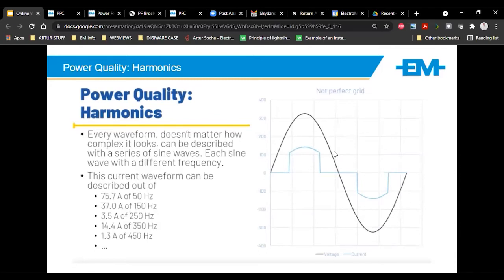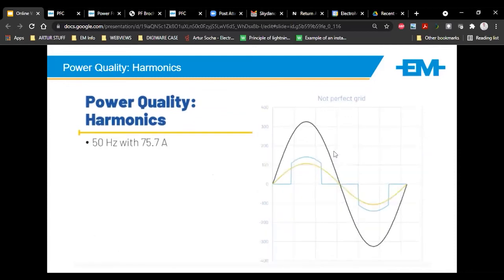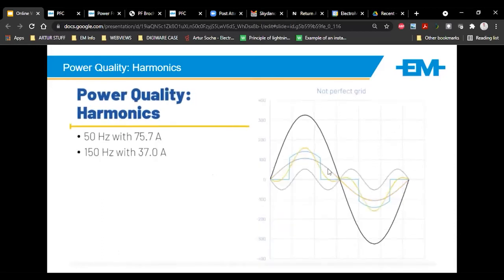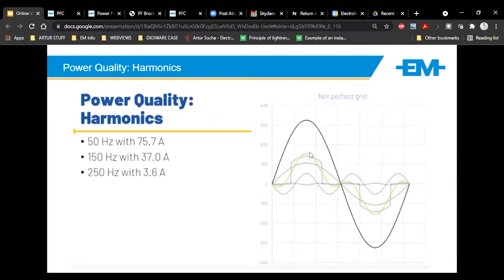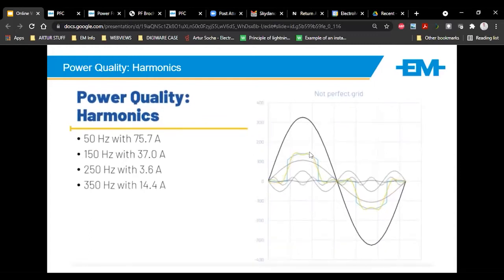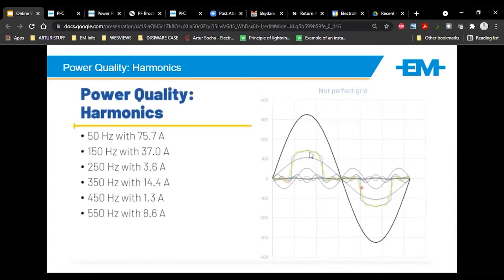So this waveform is a combination of all those different frequencies we saw before. If I had a stable 50 hertz, that would be the first step. We look at that light blue line. Then depending on where the VSD is firing, it either adds and amplifies it. You'll see that yellow now being amplified. And depending on how the harmonic order is triggering, it starts to change that waveform. If you watch the orange waveform.